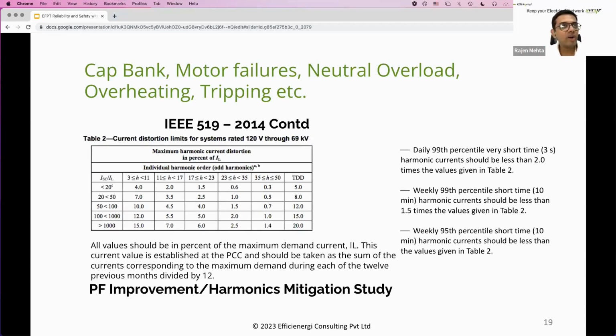PQ is very much related to fire safety, sir. As I mentioned, there are case studies where we've been able to identify incidences where there were significant unbalances in the system. Neutral overheating, for example, was just starting to happen, which was going to imminently cause or result in a fire incident. So there are a number of ways in which poor power quality can cause, or good power quality can prevent, a fire safety hazard in your facility.